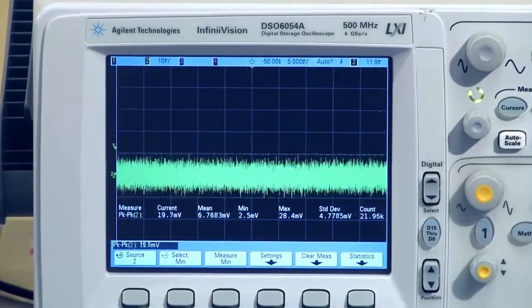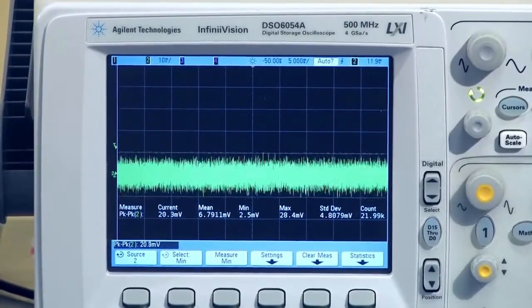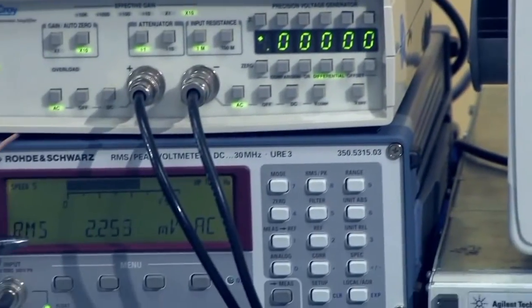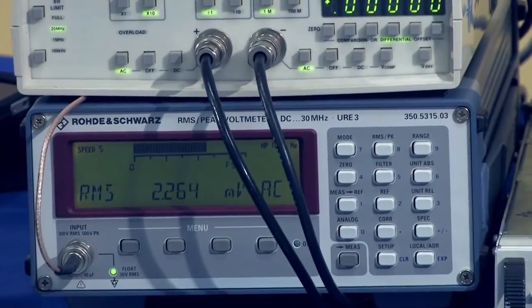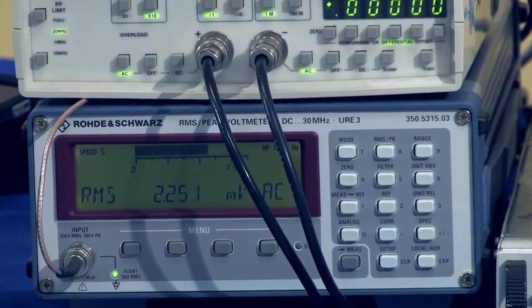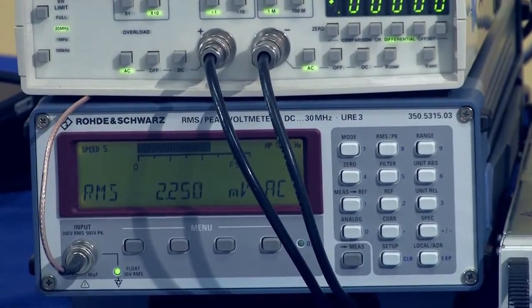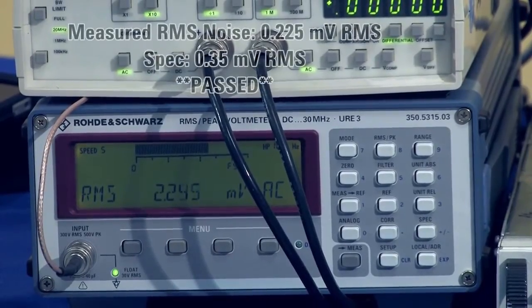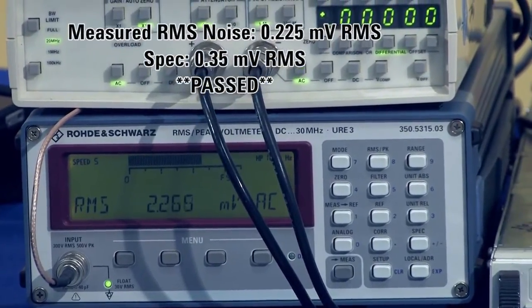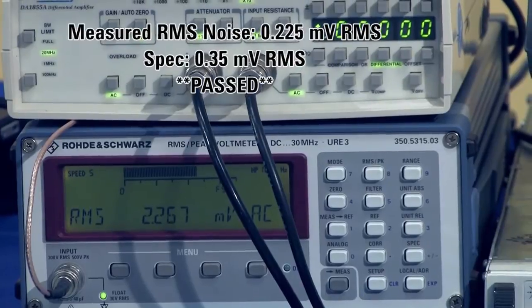The other instrument we need to look at is the RMS voltmeter. If you look at this right now, you can see that it's at 2.25 millivolts approximately. Again, it's also multiplied by 10, so it's measuring around 0.225 millivolts, which against the spec of 0.35 millivolts is within spec.